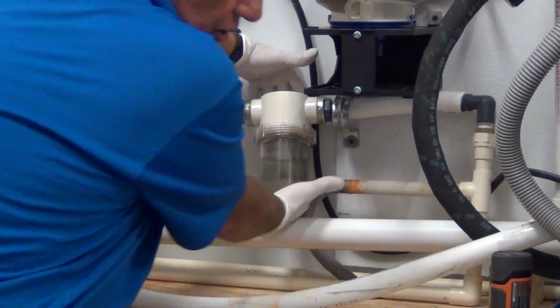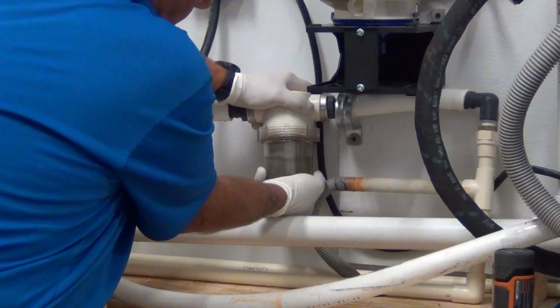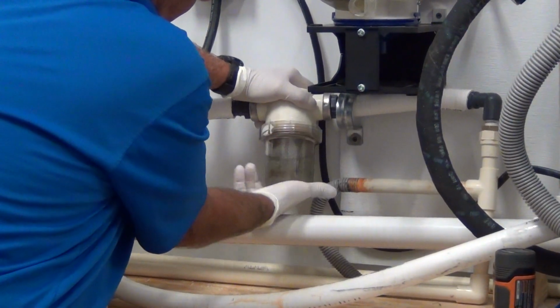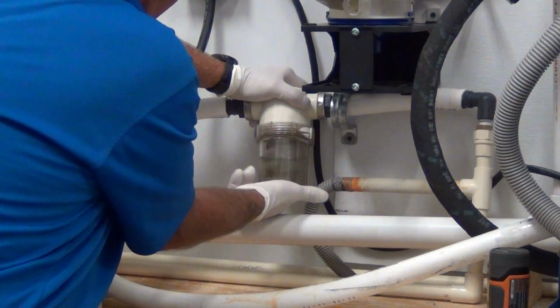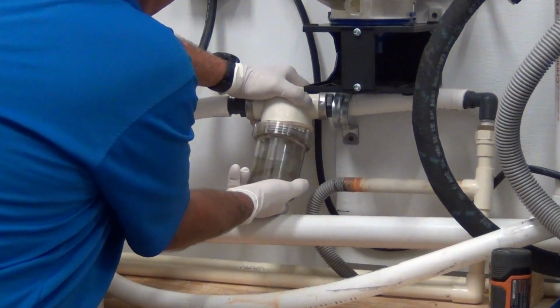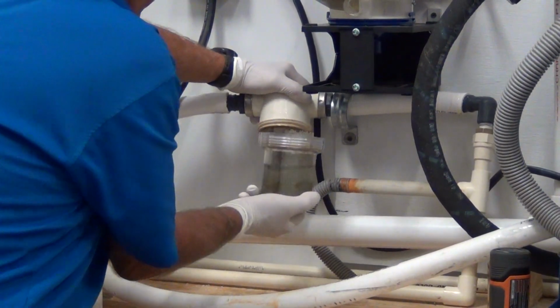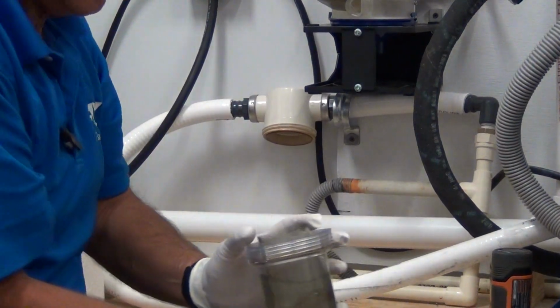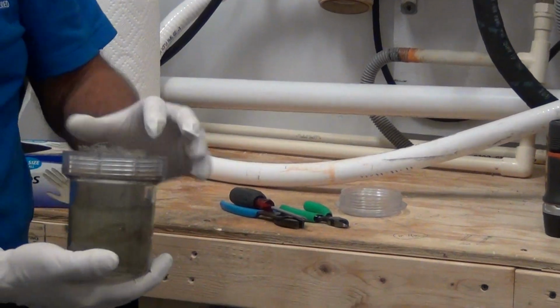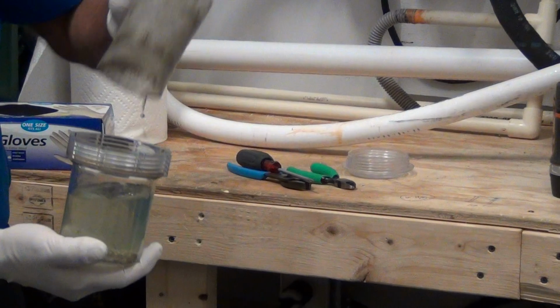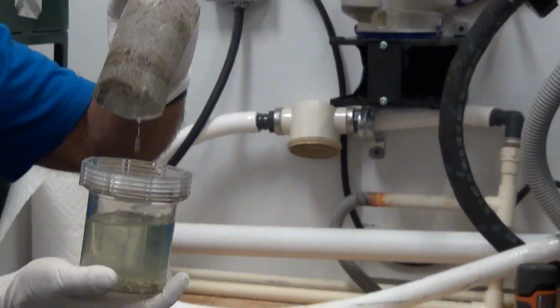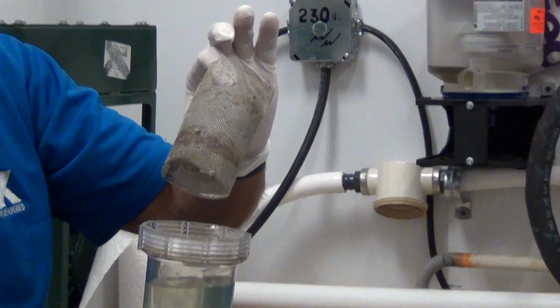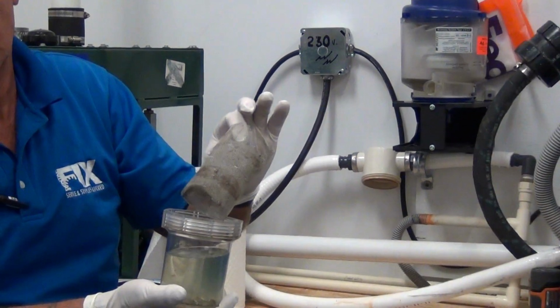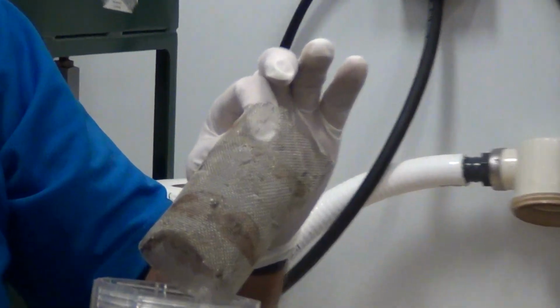Holding the top part of the solids collector, turn counterclockwise just like you're unscrewing. You're actually unscrewing. Be very careful. Pull your screen, your solids collector out as one assembly. Even if there's no debris present, you must physically pull the screen out and check the screen. The screen can get a slime on it and will actually affect chairside suction pressure.